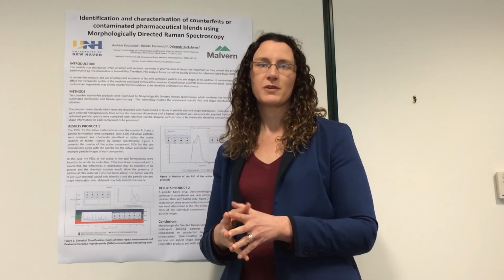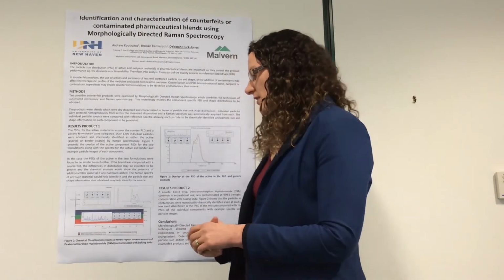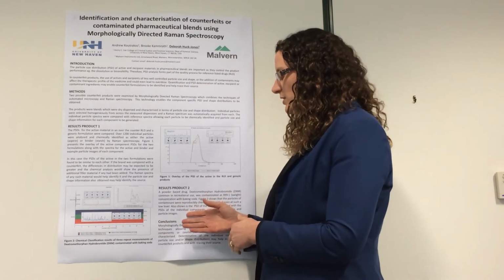The technique is basically a combination of morphological imaging, where we get particle size and shape data from individually dispersed particles, and that's combined with Raman spectroscopy. So we can go back to the particles of interest and get the Raman spectrum from each to identify what it is.